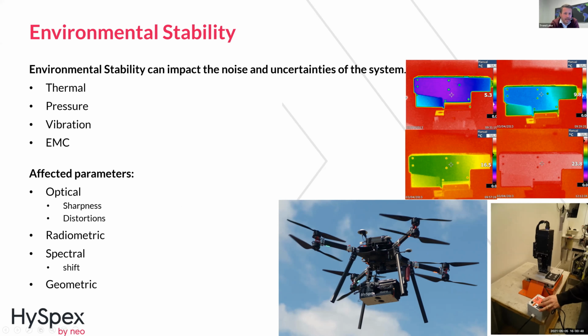So, okay. It needs to work outside a controlled environment in the lab. So you need to take care when you're designing a system about thermal variation, pressure variation, vibration, and EMC. Parameters affected by these environmental factors can be sharpness and distortions, and the radiometric accuracy can change. One thing I didn't mention in the radiometric calibration is that if you don't stabilize the FPA of your detector, for example, ambient temperature change will change the quantum efficiency of the detector, meaning that your radiometric calibration will be compromised. So if you want an accurate traceable calibration, you either need to compensate for this or you need a stabilized detector.